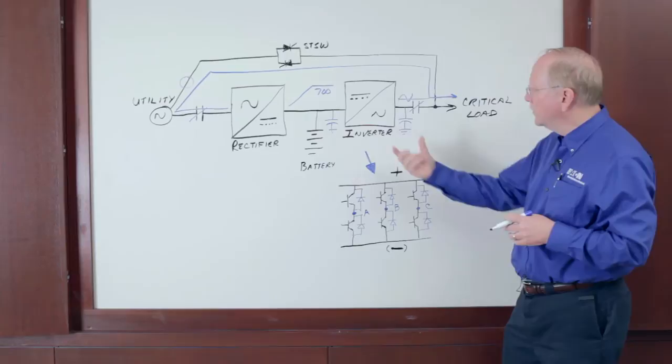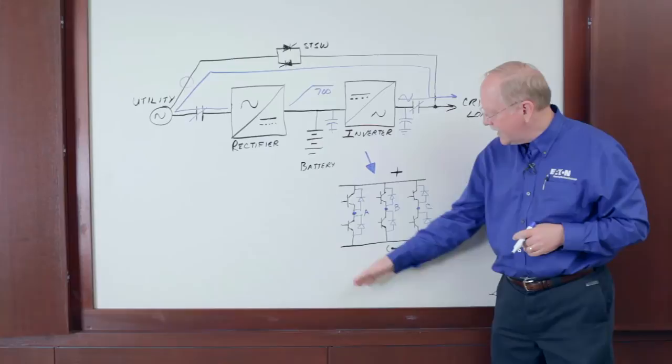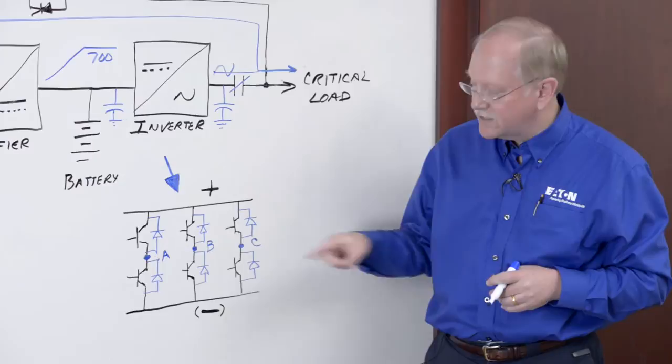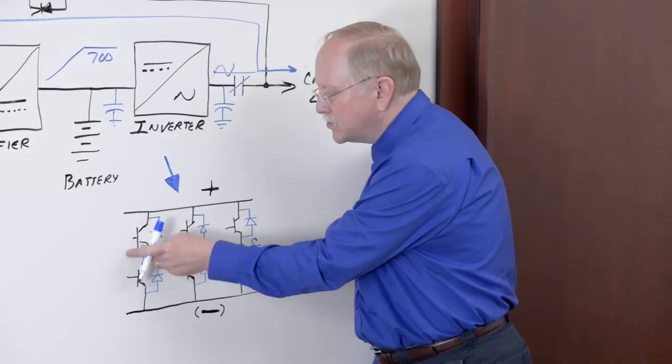But what about this rectifier that has to charge these capacitors over 30 seconds from 0 to 700 volts? How do we do that? Well, if we look at the schematic of the inverter, the inverter's job is to take DC and create AC. Schematically, it looks like this. Here's positive and negative DC, and the inverter transistors create phase A, B, and C, a three-phase AC output.